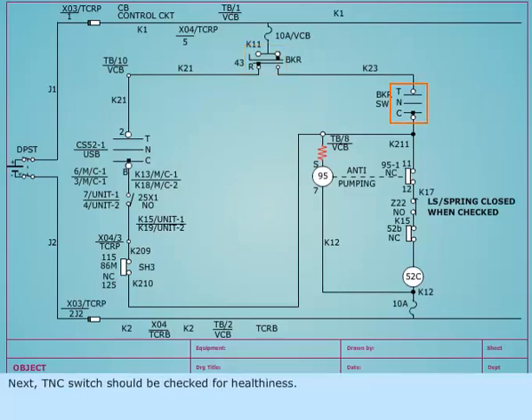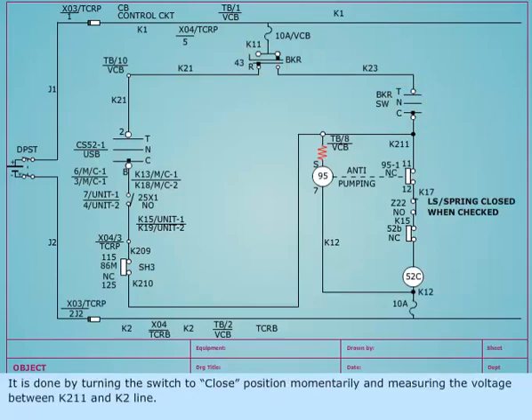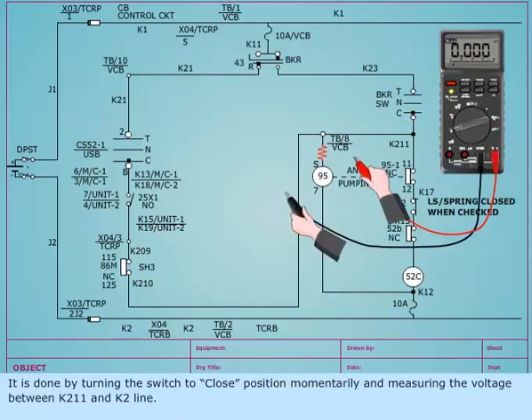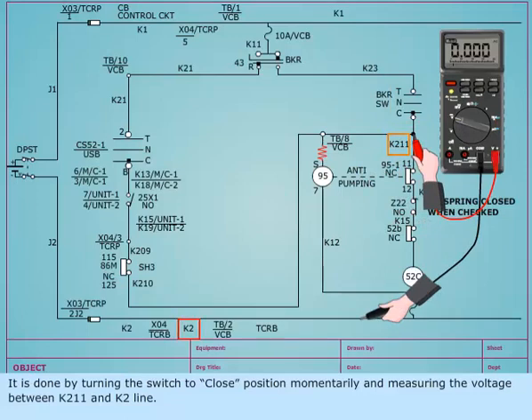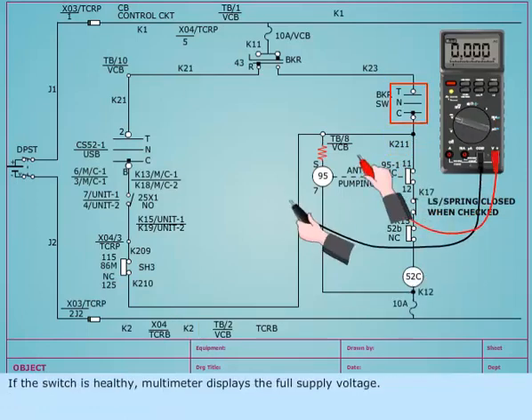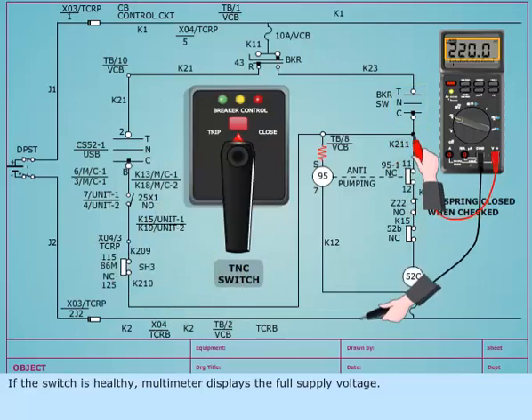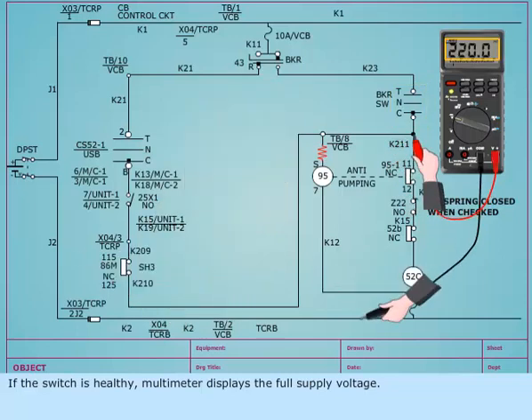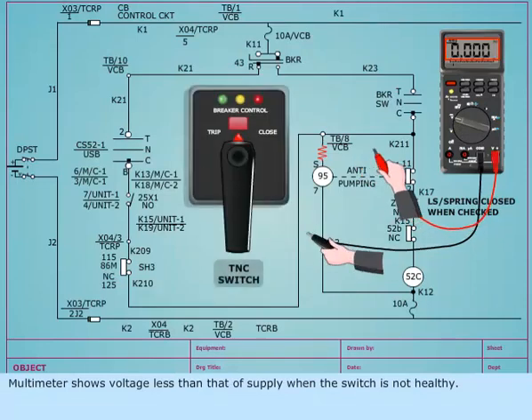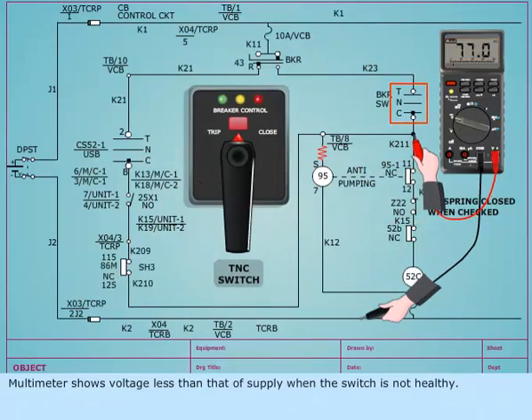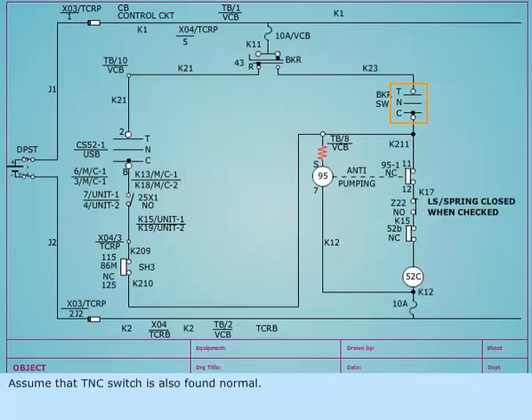Next, TNC switch should be checked for healthiness. It is done by turning the switch to closed position momentarily and measuring the voltage between K211 and K2 line. If the switch is healthy, the multimeter displays the full supply voltage. The multimeter shows voltage less than that of supply when the switch is not healthy. Assume that TNC switch is also found normal.